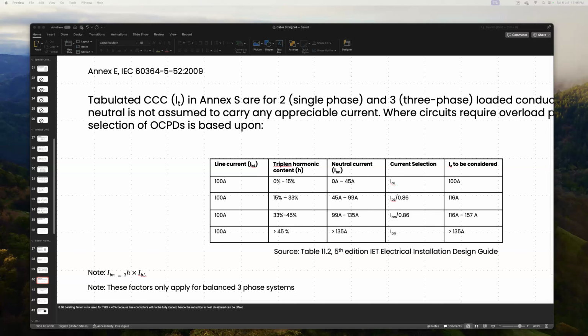Another question. In general, on ground reality, in a cable cellar room, all cables are looped and bunched together, and due to that, reactive current increases. Are you taking some factor into consideration while designing the cable? In fact, we are not supposed to take these things into consideration. These are already explained in the standard, and we have to look at the standard and make a decision.